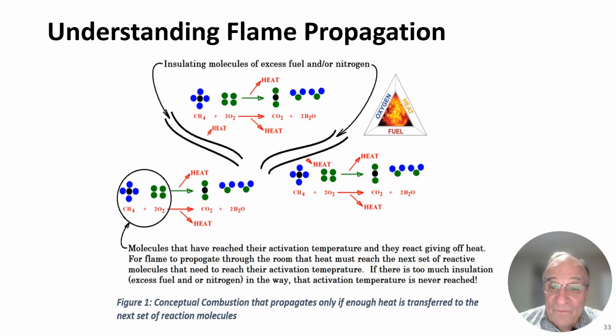15% fuel and air. But when you put an insulation barrier between this set of molecules and this set of molecules, there's not enough heat to reach this set of molecules to cause it to combust. And that's what happens if you have too much air in the room. The air acts as an insulator. So although the fuel air that went into the match flame burned, it never propagated past the match to get into this next set of molecules.